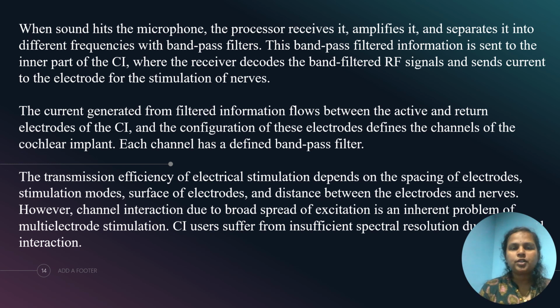The transmission efficiency of electrical stimulation depends on the spacing of electrodes, stimulation modes, surface of electrodes, and distance between the electrodes and nerves. However, channel interaction due to broad spread of excitation is an inherent problem of multi-electrode stimulation. CI users suffer from insufficient spectral resolution due to interaction.